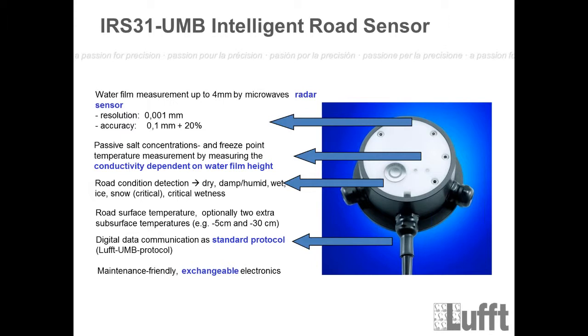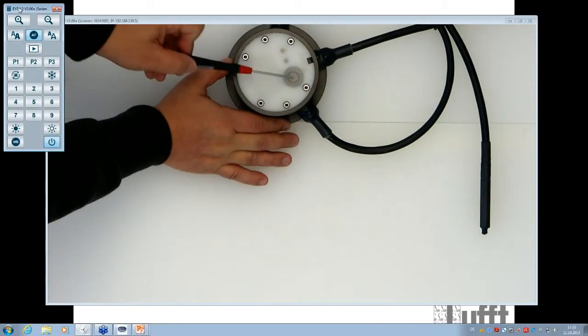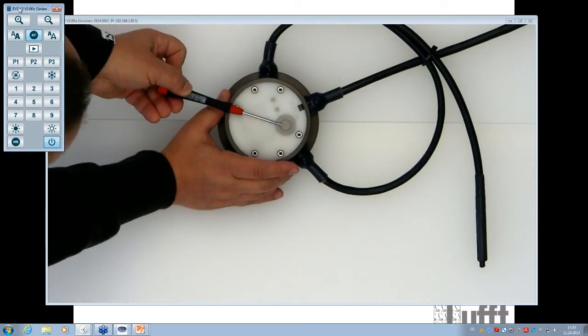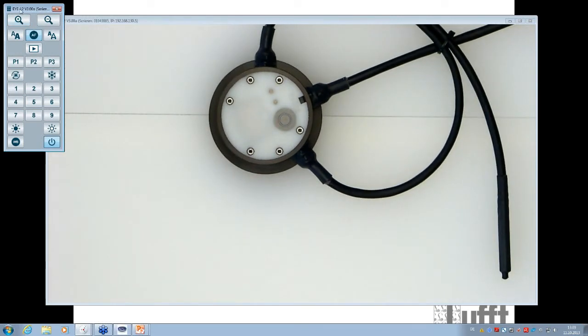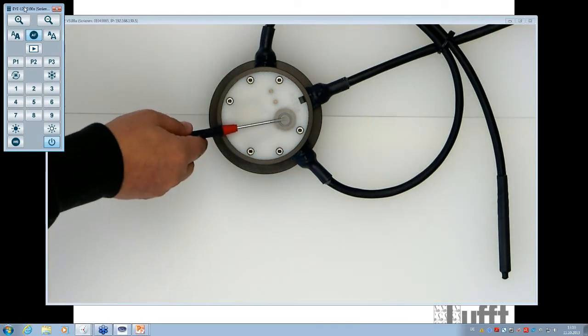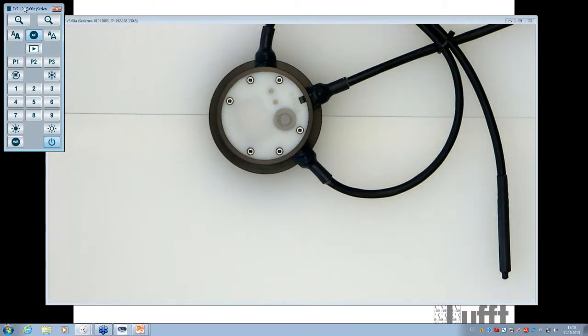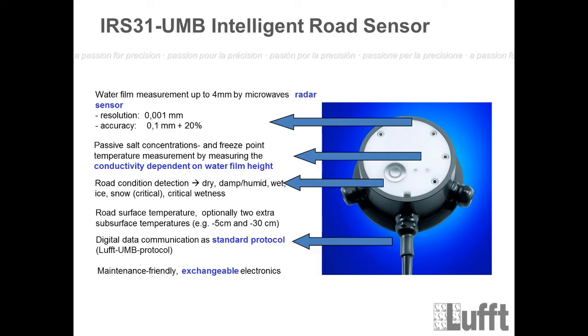This is done here, I'll show you again, under this electrode. Under this electrode we have an NTC. This is a resistor which changes its value depending on the temperature. So here we have the temperature measurement, and in addition to checking the freezing point and the water film, you can also check the surface temperature. For this you need an external, special measurement device, for example a handheld with a surface temperature probe. You can get that from Lufft, or you can use any other type of reference device to check the temperature at this point, which is the surface temperature. Okay? Right, so these are the 3 important measurements for the calibration.